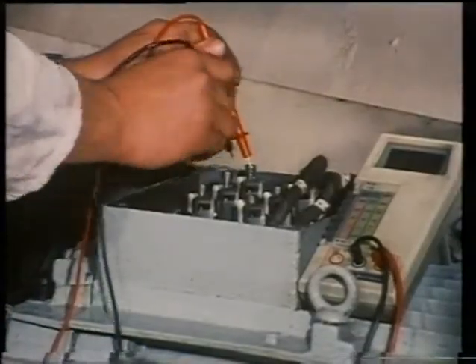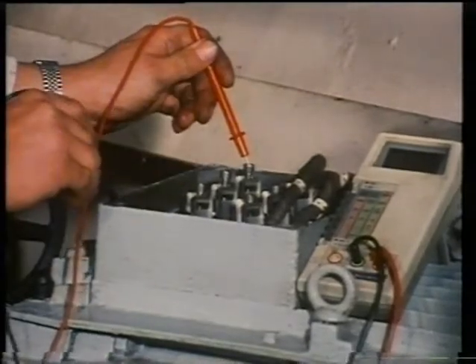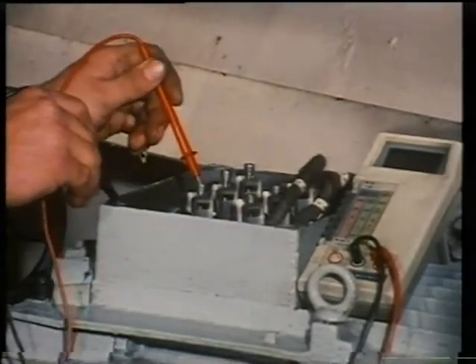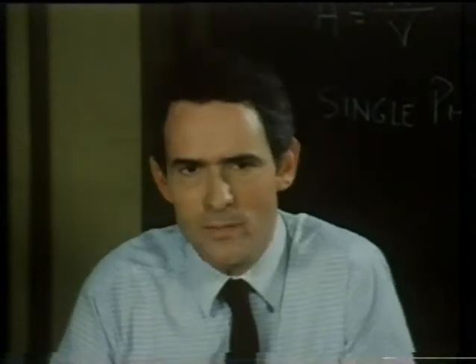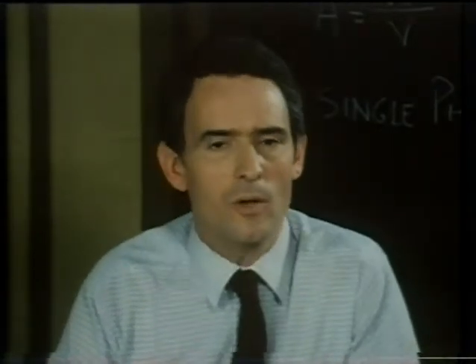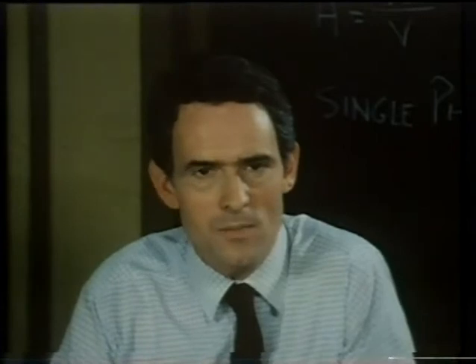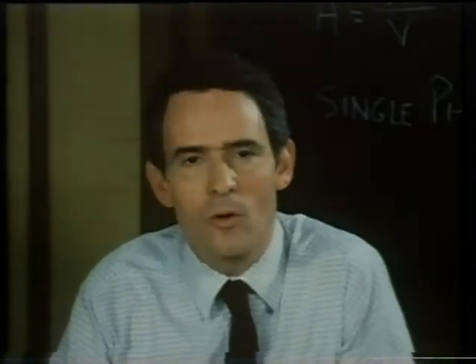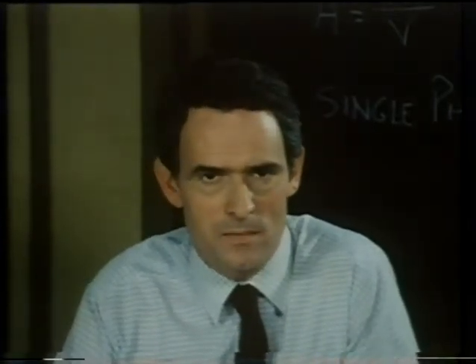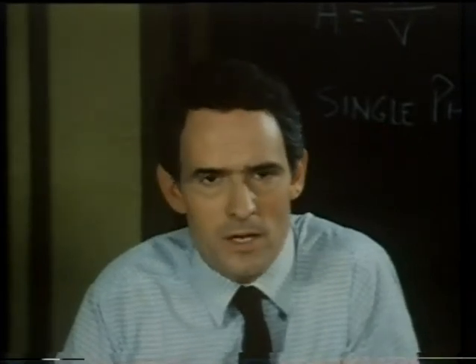Then, prove the circuit dead with a voltmeter or an approved line tester. A switchboard can never be considered dead unless all alternators connected to it are stopped, locked off, and all other supplies are disconnected. These points can never be emphasized strongly enough.